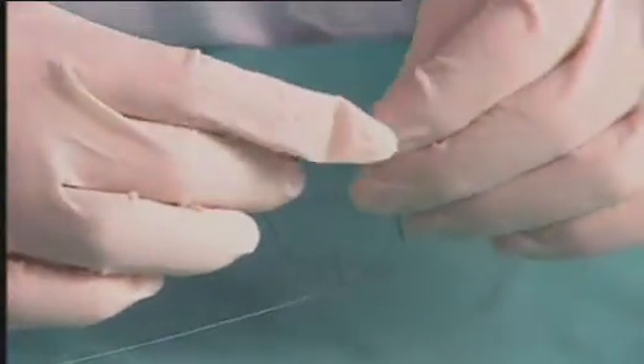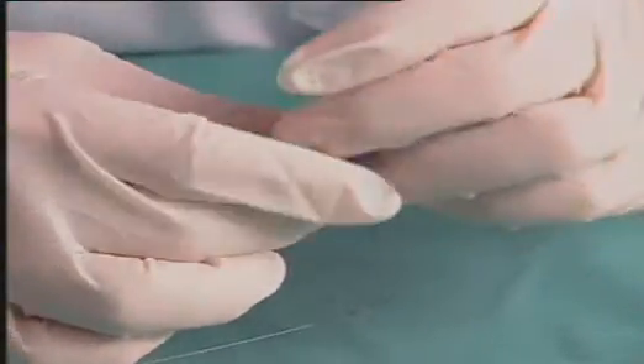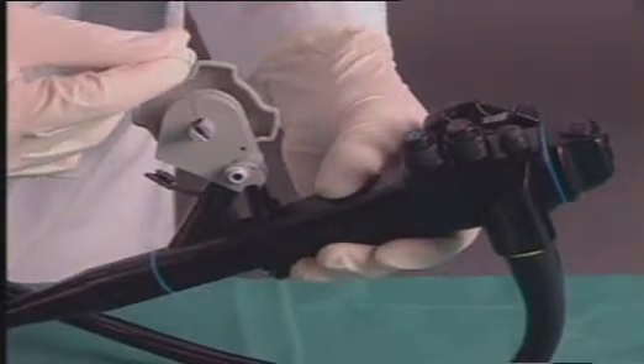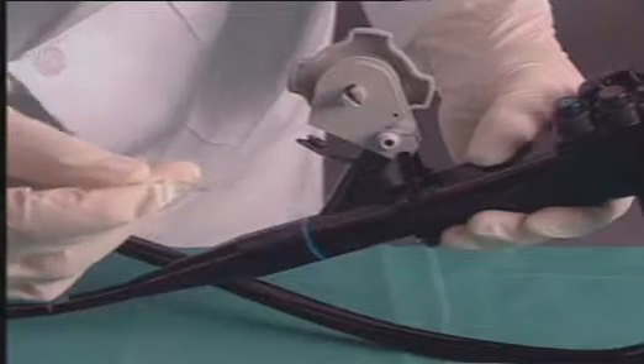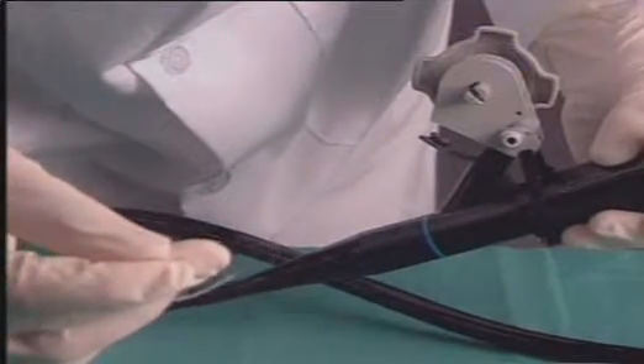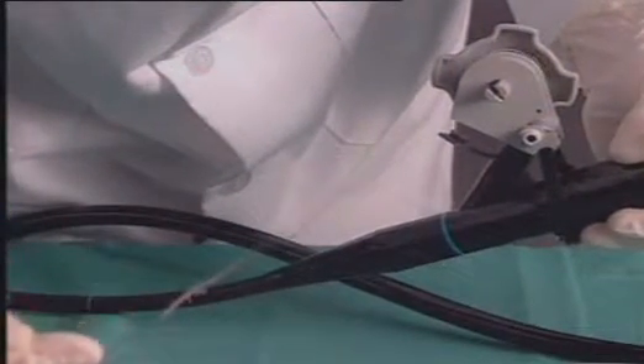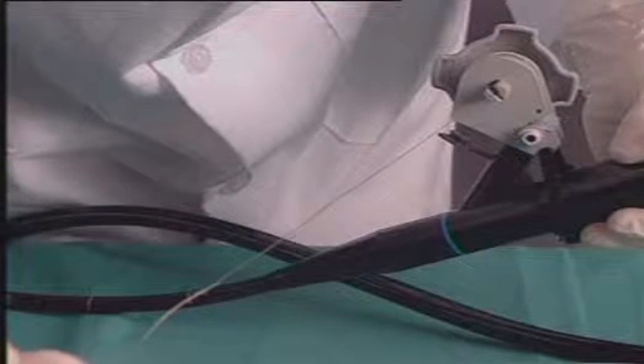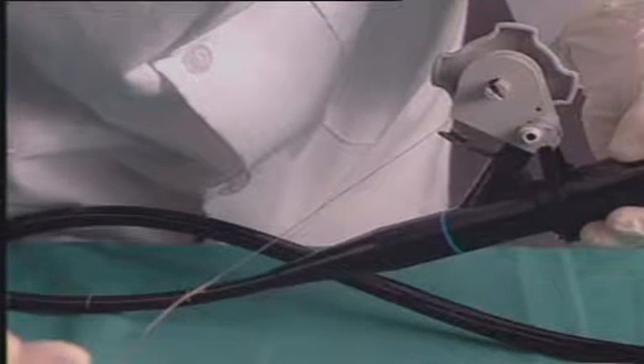Attach the pulling loop of the ligating unit to the wire loop connector on the distal end of the tripwire by threading the pulling loop through the tripwire loop. Then, threading the ligating unit through the pulling loop. Next, you will attach the Super 7 multiple band ligating cap to the endoscope. Take up the slack by pulling the proximal end of the tripwire on the handle unit. The pulling loop of the ligating unit will advance into the working channel of the endoscope.